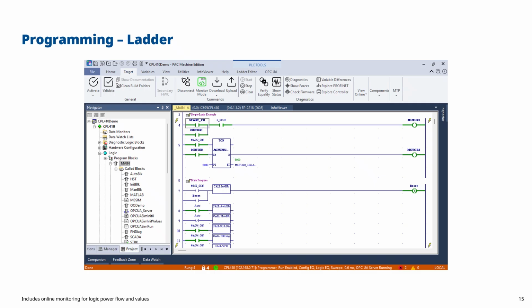On the next rung, I've got this timer function. The motor 1 contact is an input to the timer. We've got a preset timer of 5000, which is 5 seconds. On the output side, on Q, I've got a contact for motor 2, and I can see the motor 2 delay time from the ET, the elapsed time contact there. What that means is when I start my system, I hold down the start push button, motor 1 starts, and after a 5 second delay, motor 2 starts.